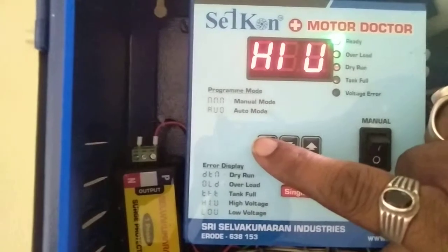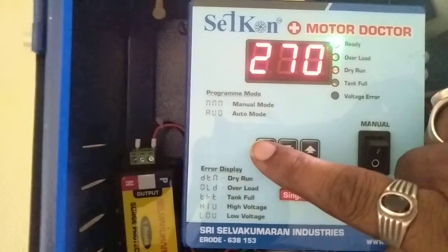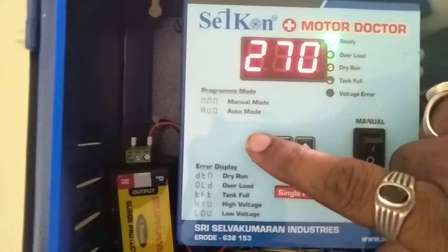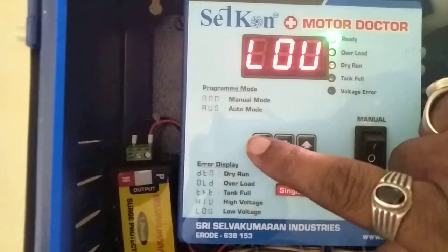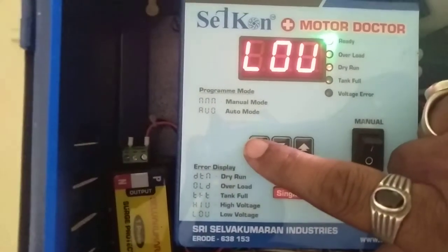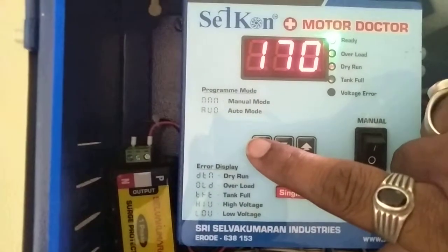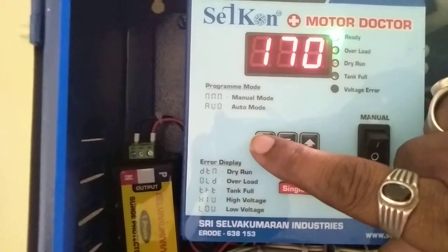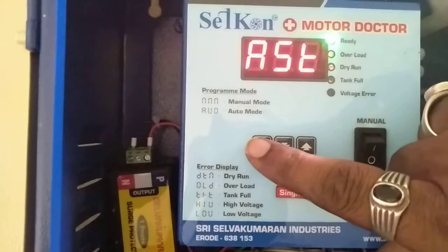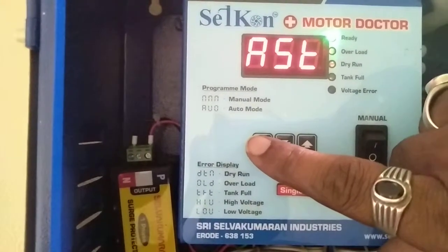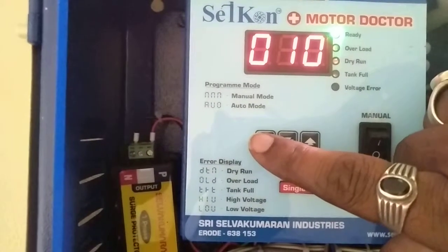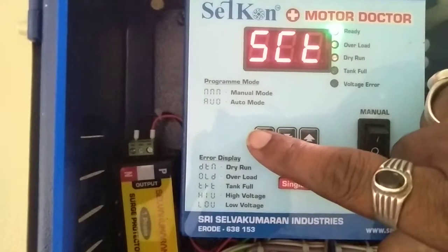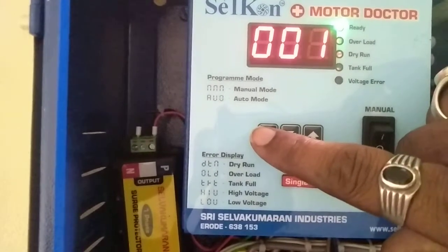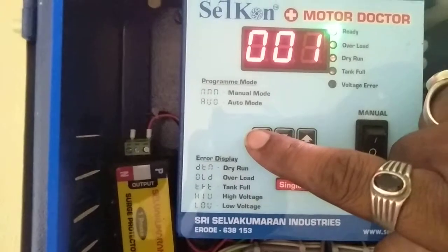Then high voltage. High voltage is set as 270. So once the voltage is above 270, it stops the motor automatically. And low voltage. Low voltage is fixed as 170. So if the voltage is below 170, it protects the motor. Auto start time. So once the power resumes, the motor starts automatically after 10 seconds. Then starting capacitor. We fixed the starting capacitor time as 1.